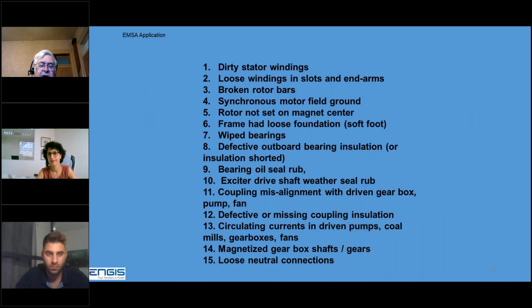Here's a list of conditions found with motors. Dirty stator windings are by far the number one problem with motors. The end windings and end arms can get loose. Most modern motors are VPI'd, so they're glued in the slots, so they don't become nearly as loose as the older ones do. Broken rotor bars is very common if you've got a big fan you're starting. We have picked up field grounds on a large synchronous motor. Not setting a motor on a magnetic center, the rotor will thrust back and forth. We can pick that up.